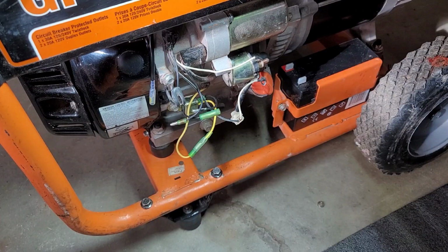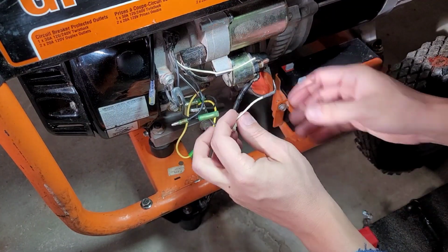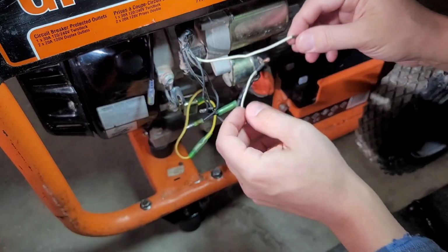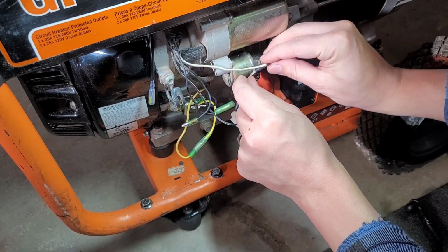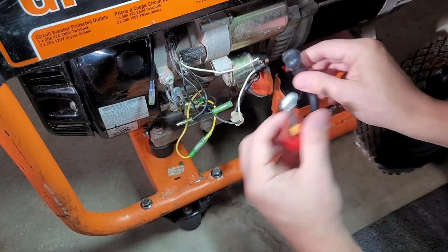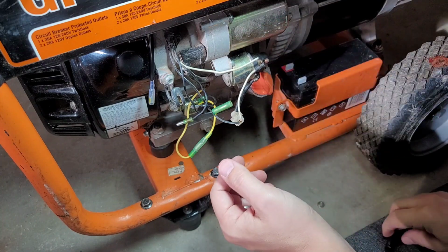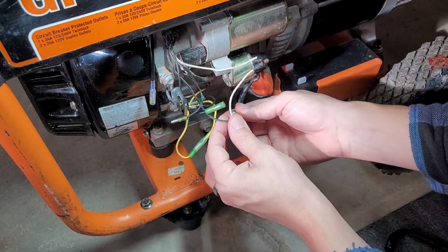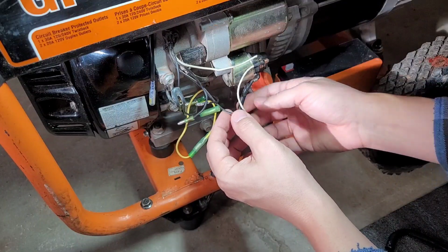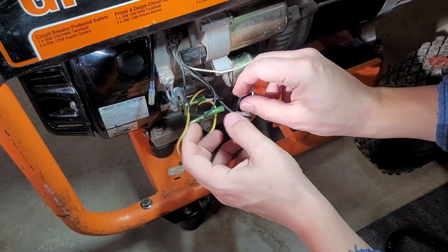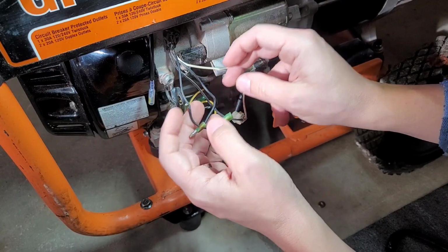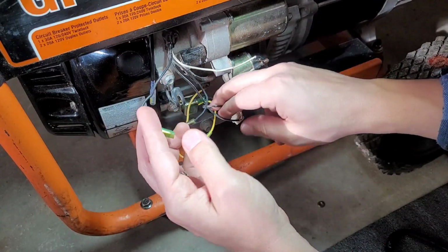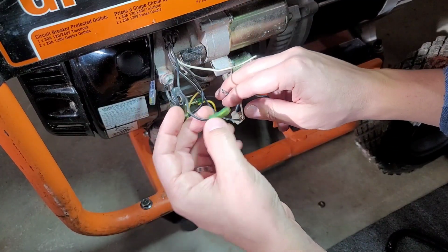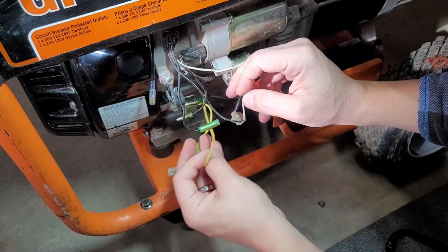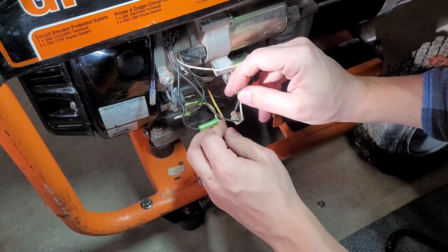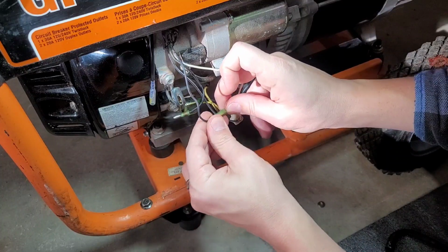Now here on the 12-volt system, we have a few things going on. We have two ring terminals coming from the panel; they're going to go to the battery side of the starter contactor, and then we'll put our 12-volt battery terminal there. There's a white Molex connector that goes to the contactor for that, and then we have these wires left. This one here goes to the low oil switch, so it's yellow to yellow, and this will go here.